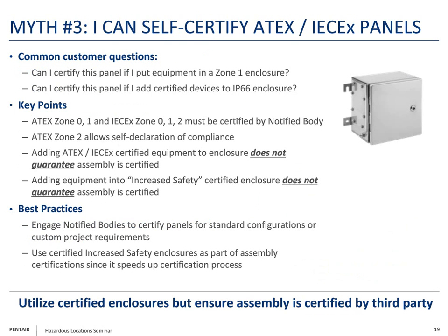One of the biggest challenges that we see with ATEX and IECEx control panels is customers asking, well, how does this whole system get certified? So in the UL world, there are UL certified control panels or even ETL certified control panel programs that integrators or OEMs can get engaged with those certifying bodies so that they can do some certification of Class 1 Division 2 or Class 1 Division 1 control panels. In the ATEX and IECEx world, that doesn't really exist. There's no control panel or systems integrator program.